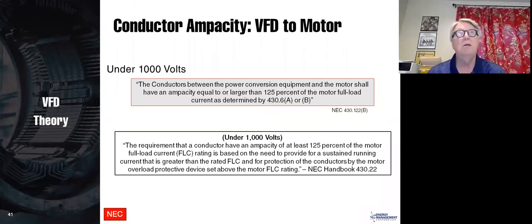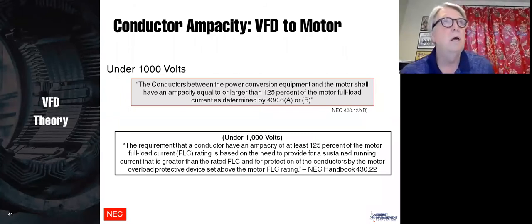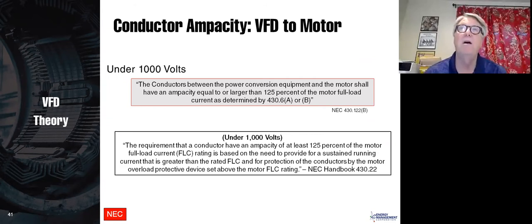Now, how about the cables coming into the VFD? By code, they are also rated for 125%, but it's 125% of the input amps to the VFD. Well, what are the input amps to the VFD? It gets complicated. And being a VFD manufacturer, I really like that because I can say they are whatever I want them to be. Because if you have a passive harmonic filter, a 12-pulse drive, an 18-pulse drive, an active front end, or reactors, all these things change the input amps to the drive. So most people actually just use the same cable on the input as on the output, and the input cable is 125% of the motor full load amps. I actually think that's fine.